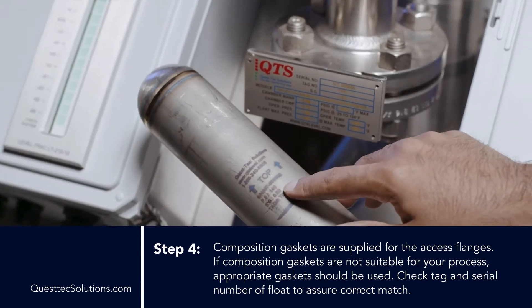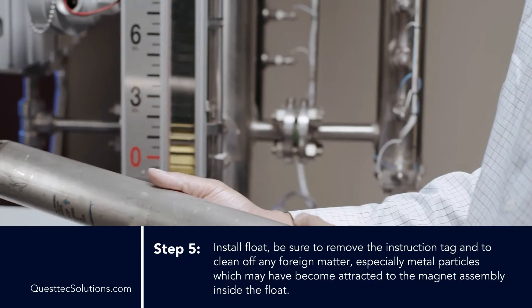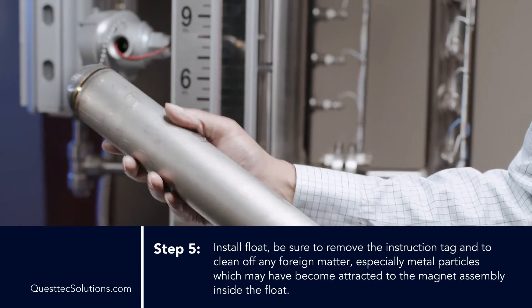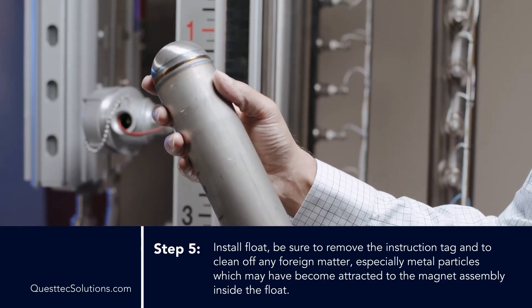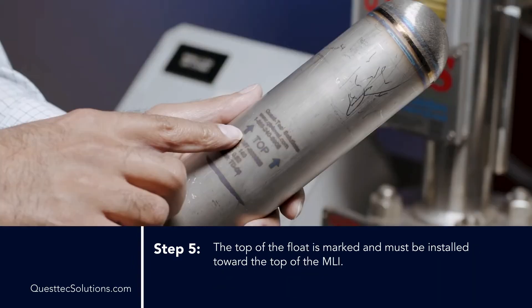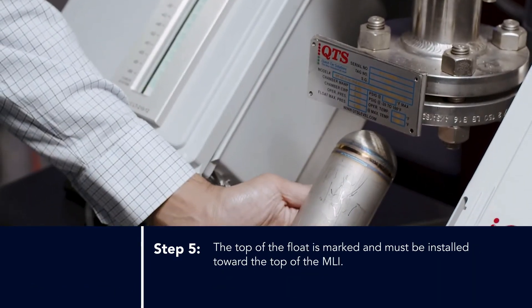Check tag and serial number of float to assure correct match. Step 5: Install float. Be sure to remove the instruction tag and to clean off any foreign matter, especially metal particles, that may have become attracted to the magnet assembly inside the float. The top of the float is marked and must be installed toward the top of the MLI.